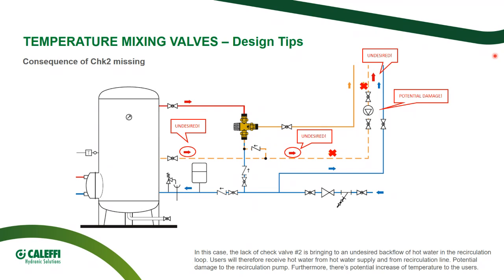With the same method, let's try to forget check valve number 2. Check valve number 2 is protecting the water coming from the recirculation loop towards the hot water storage. If we are missing it, we might have undesired backflow of hot water from the storage backwards to the loop. So I might have potential damage to the pump because it is facing backflow. Also the temperature within the recirculation loop will rise. So there will be lack of comfort and potential danger for the final users.